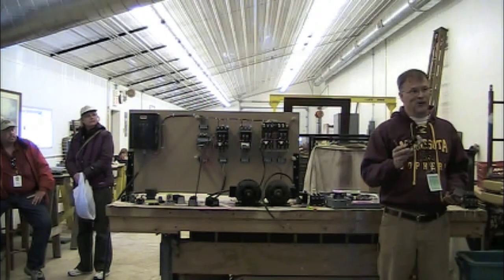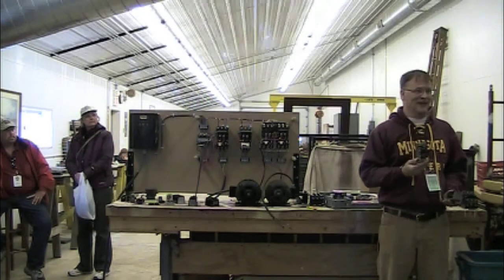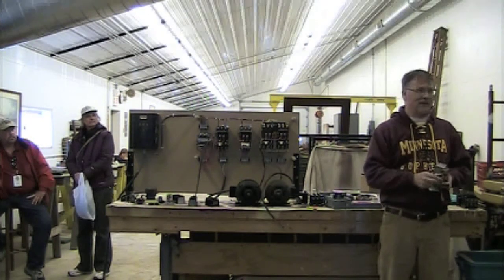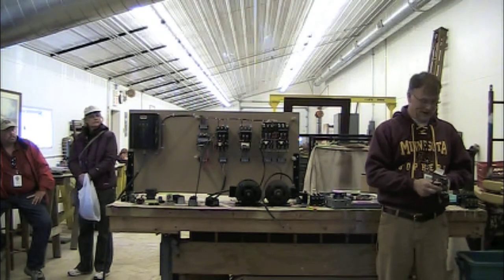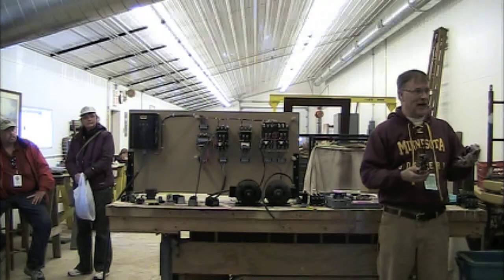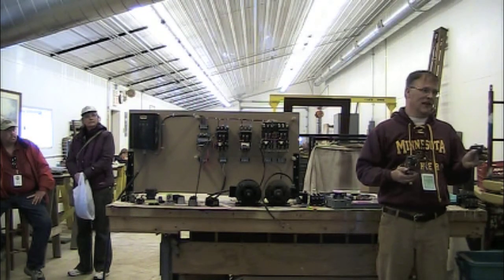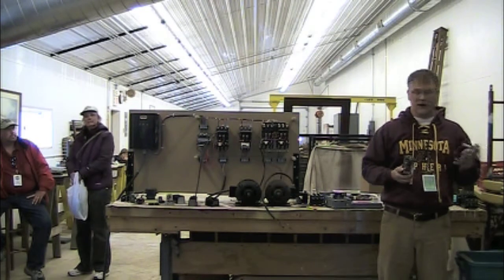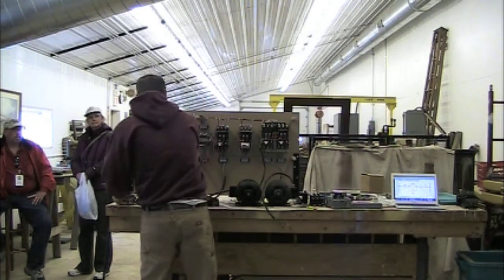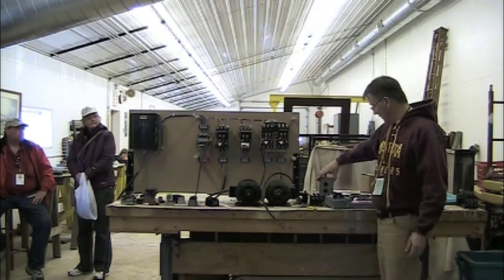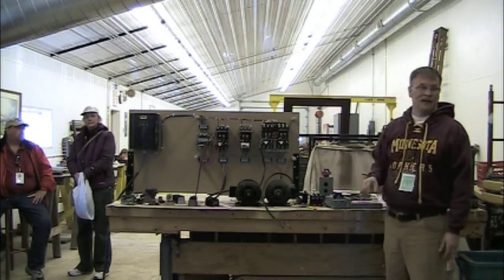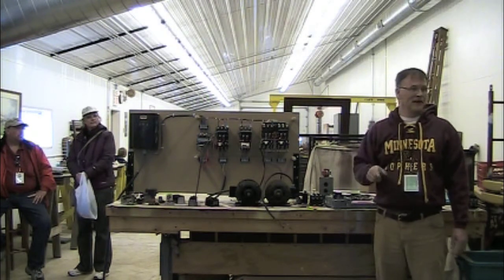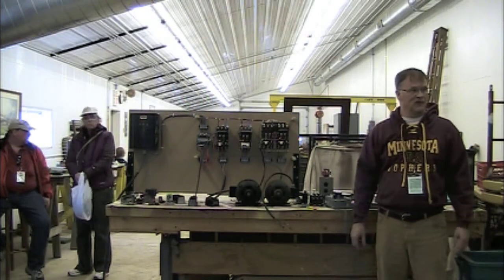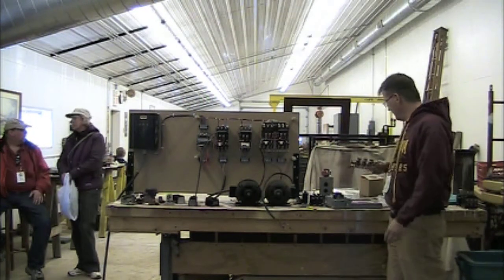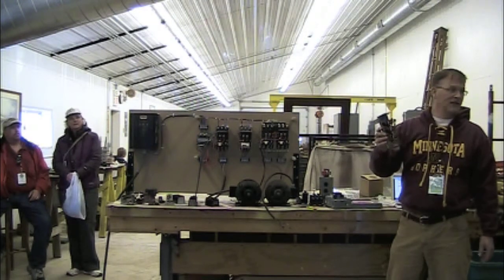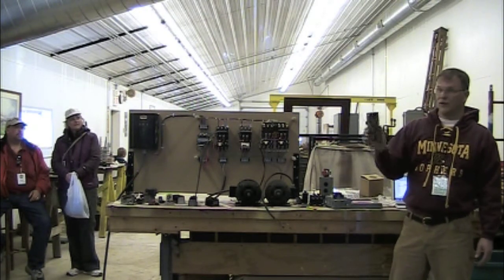I just noticed when I was pulling all these out of the drawer that this one's actually missing it. So I can put a jumper on there, and the side that I jumper is just going to be terminal 2 on here. That's just something you need to be aware of. On these composite start-stop stations that have the stop-start buttons all integrated into one, it's already there. But if you're building it out of the box and putting all the pieces in it, you always have to provide that jumper in that circuit, because your stop switch and your start switch are going to be separate. For most of the things, like this one, this is a 2-speed start stop. I haven't even looked at this, we just pulled this out of the back of Doug's truck.